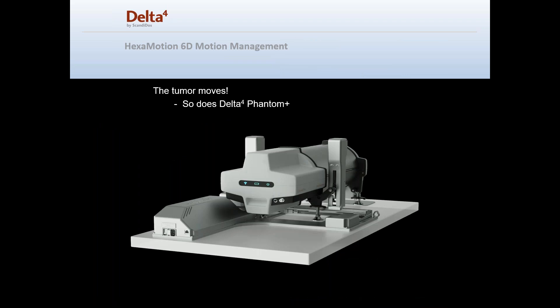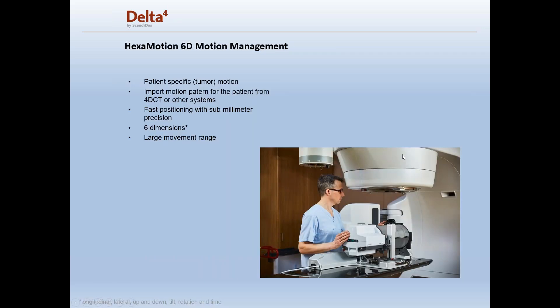The second piece of the motion management system is the HexaMotion. The HexaMotion is a platform used to cradle the Delta IV Phantom Plus and actually move the phantom six-dimensionally, allowing you to move your tumor and track it during your QA process. The HexaMotion 6D motion management system allows you to move the tumor specific to the patient's treatment plan and specific to the 4D CT image set.